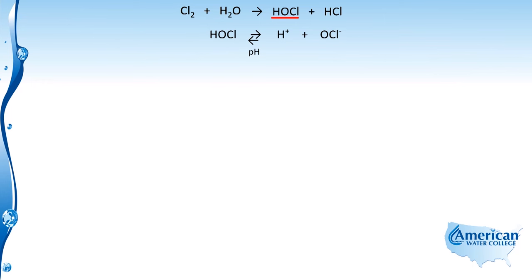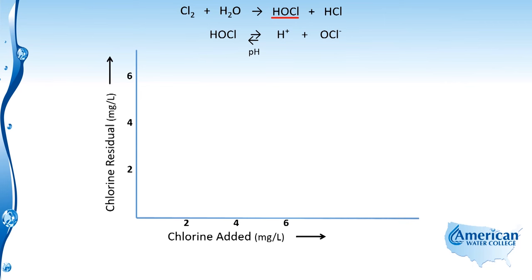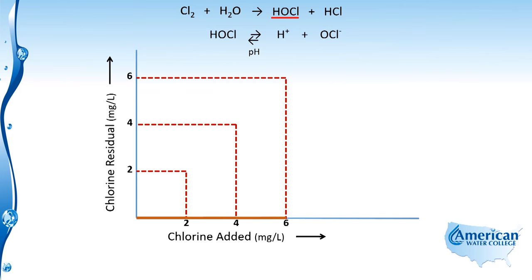Since there are no impurities in pure water for chlorine to react with, we expect our measured chlorine residual to equal the amount of chlorine added. For example, if we add chlorine at a dose of two milligrams per liter, we would expect a two milligram per liter residual. This also holds true if we increase the chlorine to four or six milligrams per liter — there's a linear, direct relationship between the amount of chlorine added and the residual that remains in solution.